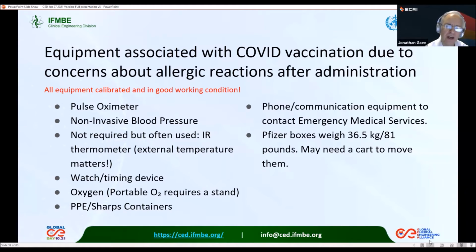In a lot of places, they use some sort of IR temperature screening on people, and you have to take care when using IR thermometers. Remember, they were developed for use inside. The IR thermometer is expecting internal temperatures. When COVID first started, I had a colleague in Detroit, Michigan. It's very cold there in the winter. They had patients lined up outside for screening, and they recognized immediately that their IR thermometers were not working well. They were giving very inaccurate results. So they had to change the system, either screening people in the lobby or creating tents outside where the temperature could be closer to indoor temperature. So if you're using IR thermometers, especially outside, watch out.